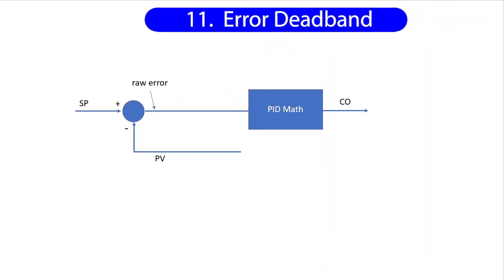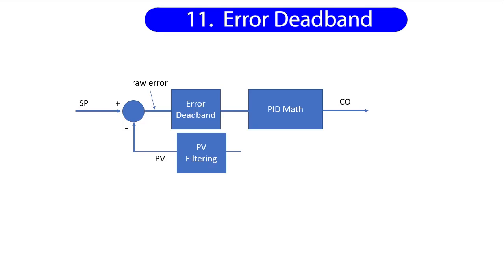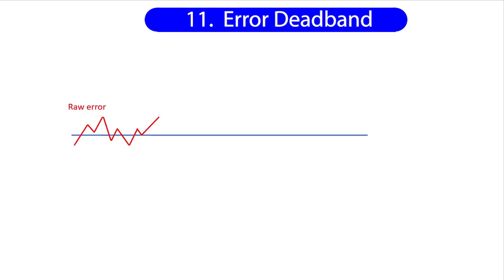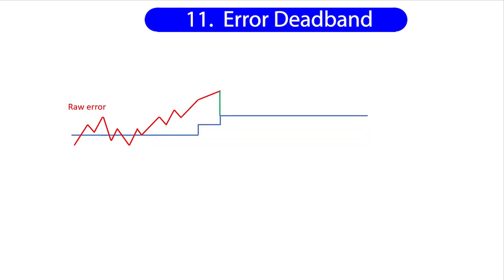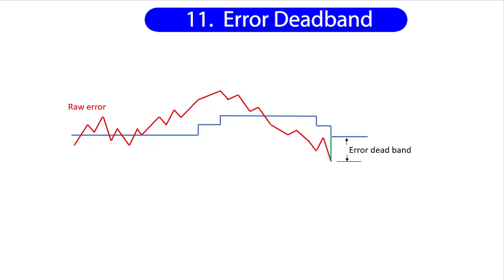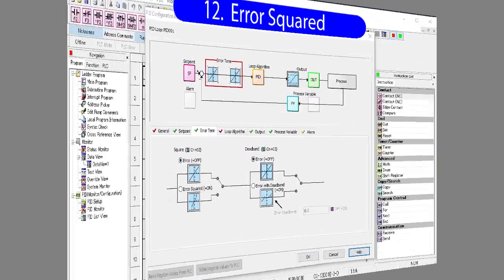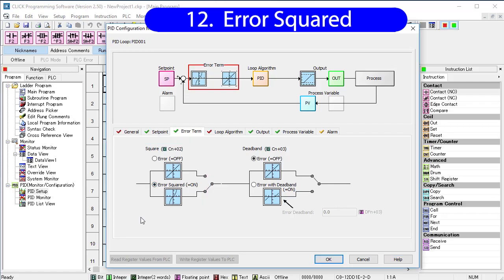So filtering filters the process variable before it gets to the PID stuff. Error deadband provides another kind of noise reduction, but it does it on the error signal. I envision the error deadband as a string. One end is tied to the error signal coming into the error deadband and the other end is tied to the signal coming out. If the incoming error moves enough to pull the string taut, then the resulting signal moves. As long as the string is slack, the resulting error stays the same. Again, you want to keep this as small as possible or it will slow down the PID response. This guy squares the error. So errors smaller than one get reduced and large errors get amplified. That will make your system less responsive to small errors which helps reject low noise levels. Notice that this gets applied before the error deadband.